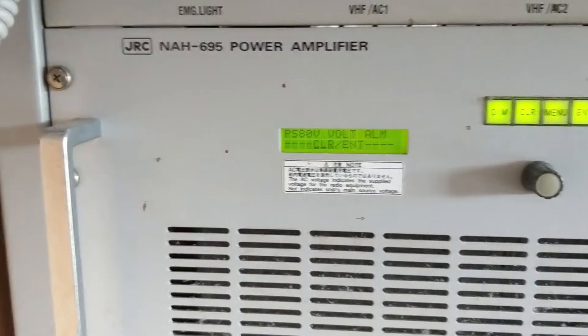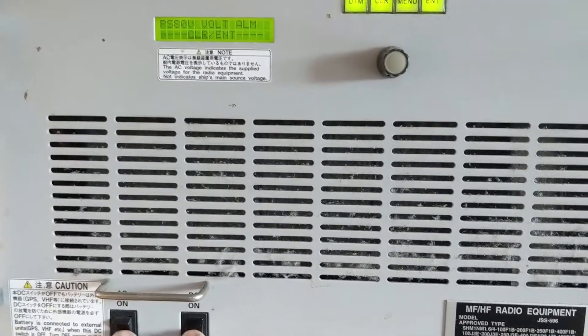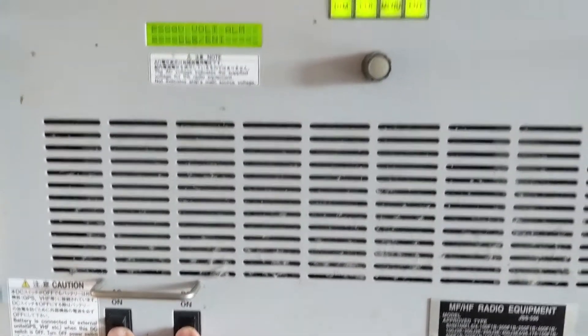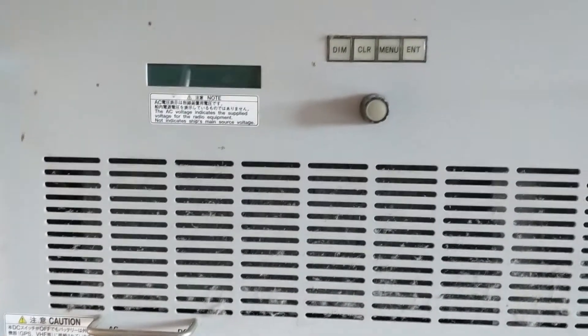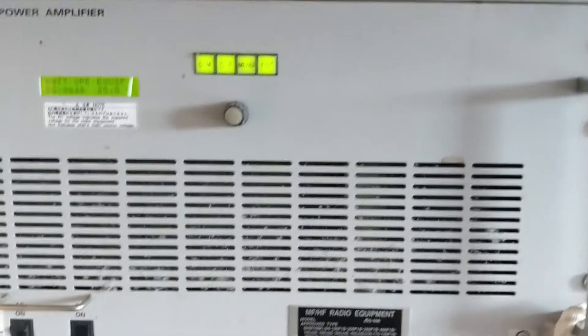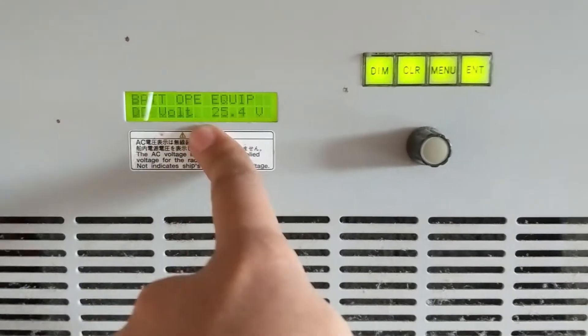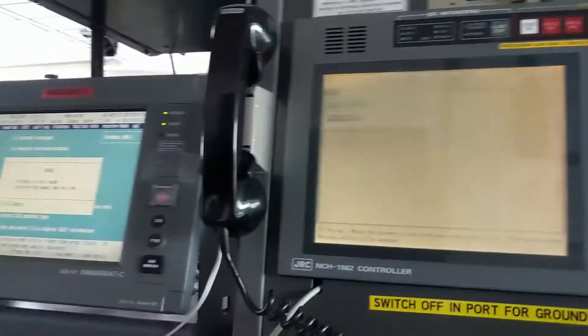If we check and switch off, then switch on only all direct current — let's see what happens. You can see battery operation equipment. This is only on direct current now and the battery is showing 25.4 volts, so it is still okay and all the equipment is running. Okay, that's it — there is no more alarm and we have acknowledged.